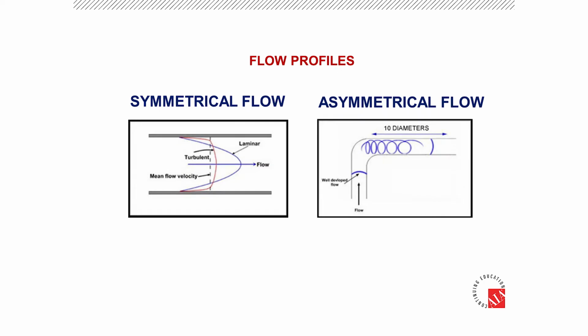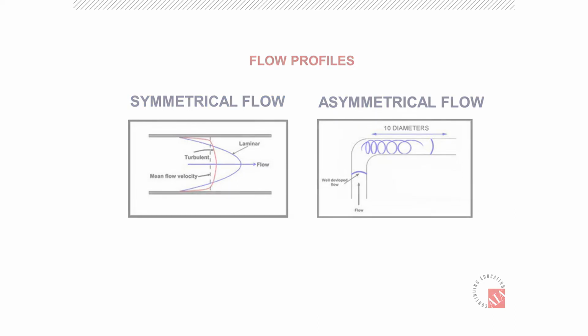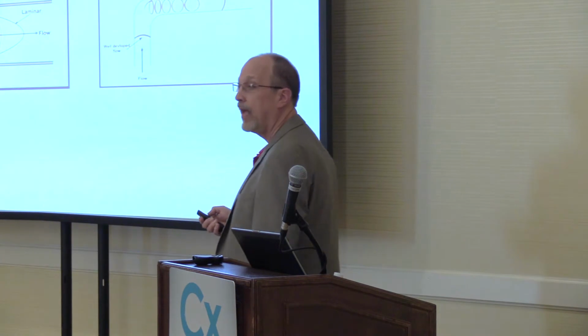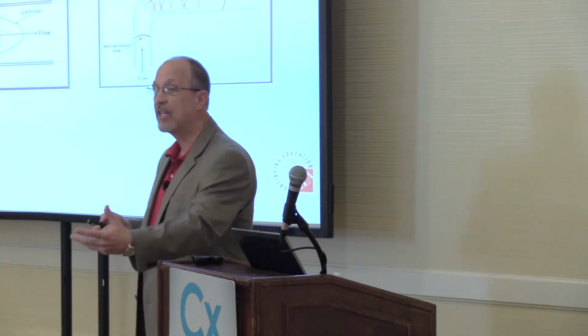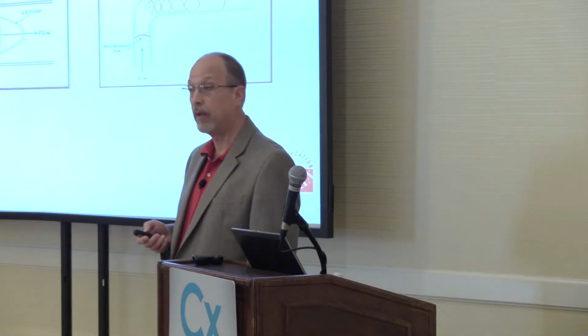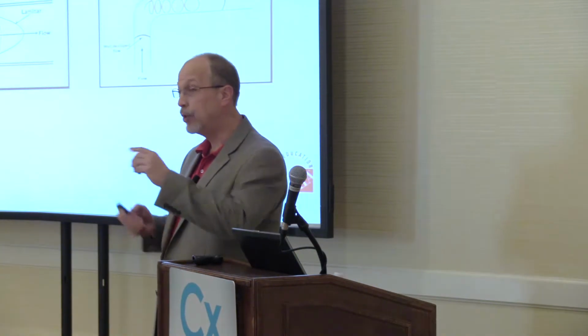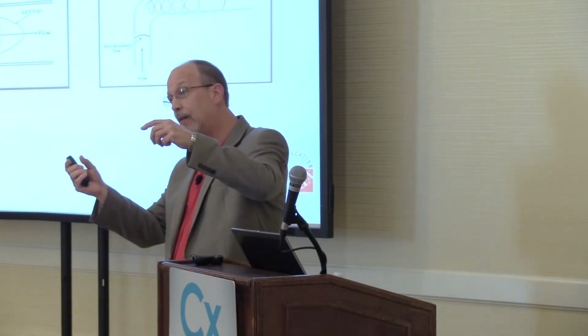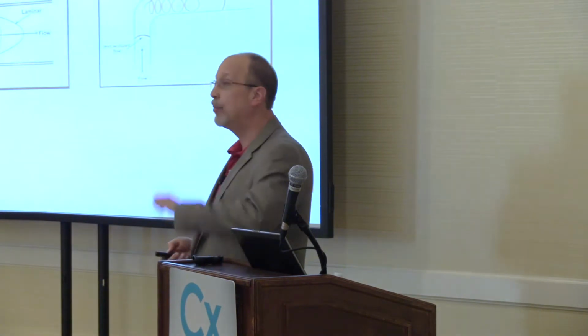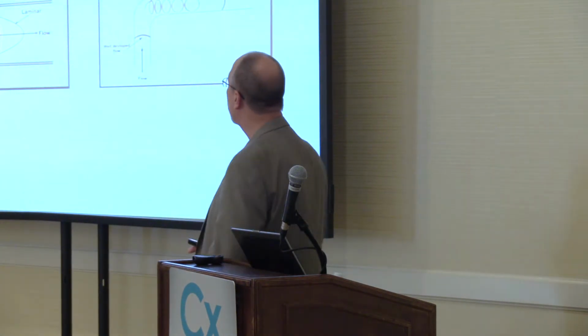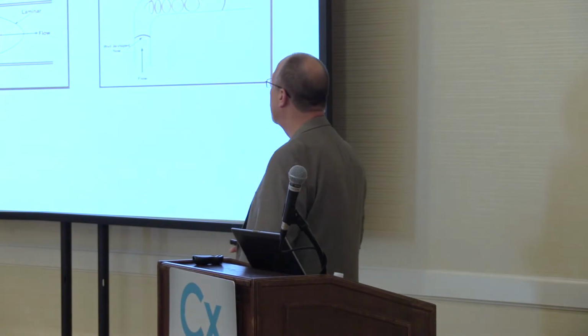So here's the 10 pipe diameters. If I was to put my sensor right here, I'd have a good application. If I was to put my sensor right here, what would happen? You may have excessive turbulence and the math may not work. So you may have to profile, move your sensors to actually catch a signal. That can be problematic and that can affect the overall accuracy of your device.